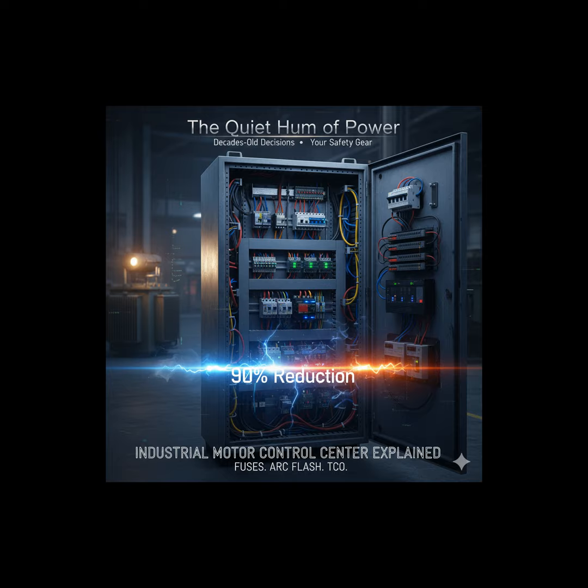We've used that term, selective coordination. For those listening who might not work with high voltage every day, why is that so important, especially in a place like a hospital? Selective coordination is the ability to ensure that when a fault occurs anywhere in the system, only the protective device nearest to the fault trips.